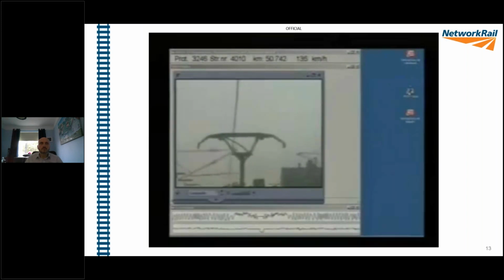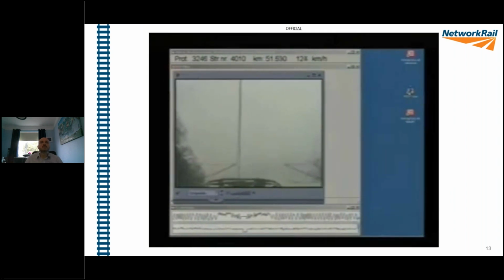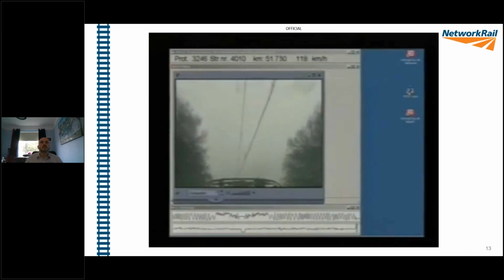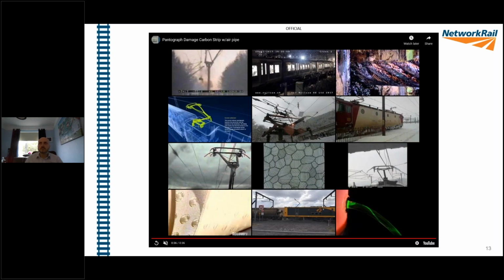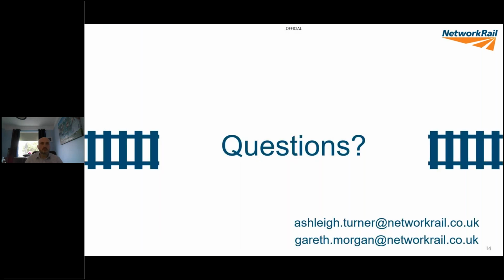Still a failure, unfortunately caused by an overhead line failure again. Something hanging off a registration arm that shouldn't be there. But as seen at that impact point there, the pantograph automatically fell down. And as you see, the contact wire is still very much still up in the air. So there may be some damage on that one structure, but instead of 1 kilometre of damage, we only have perhaps 1 or 2 spans of damage at the most. And I think that leads us on nicely to questions.